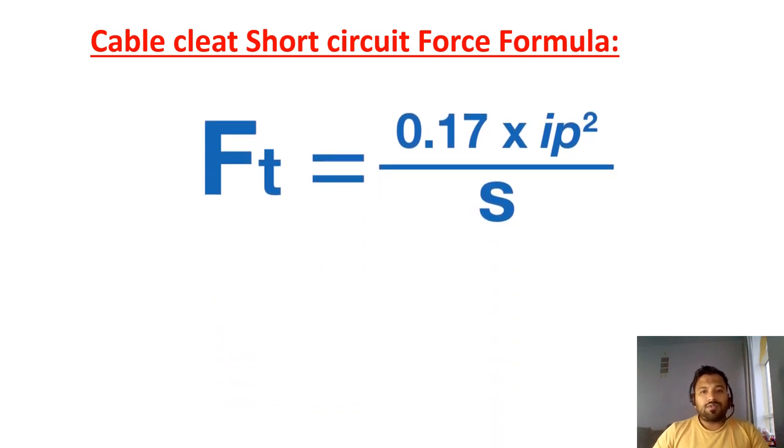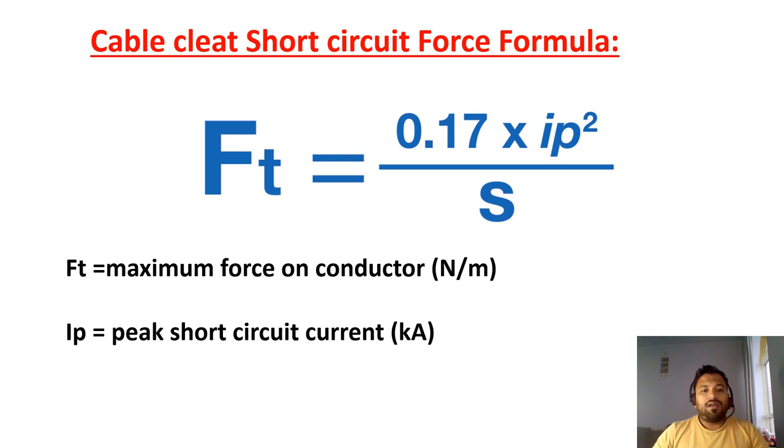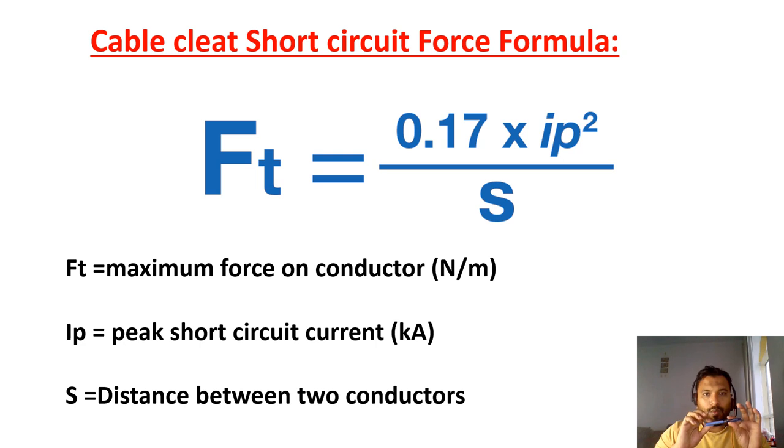Ft is equal to 0.17 into Ip square by S. Where Ft is equal to maximum force on conductor. It is represented in Newton per meter. And then this 0.17 is a factor. Ip is equal to peak short circuit current. That is in kilo amperes. S is equal to distance between two conductors in meters. So this is the formula. With this formula, we can know each conductor, what is the force applying on each conductor. So if we know this one, we can select the cable cleats easily.